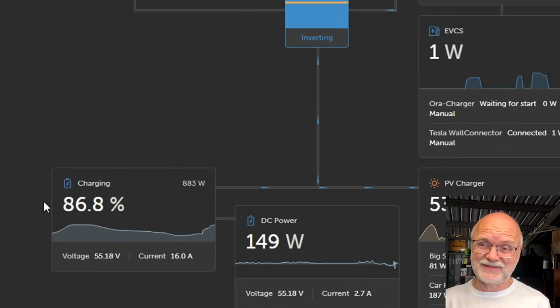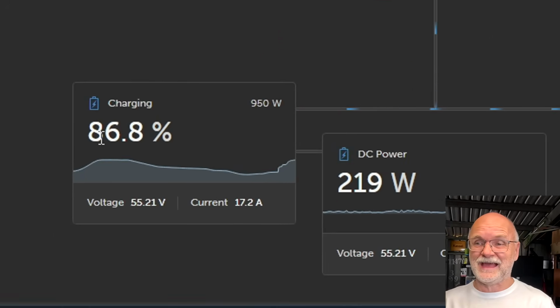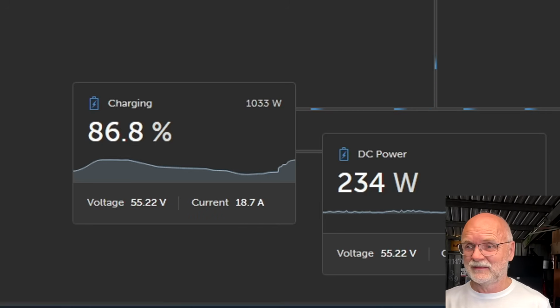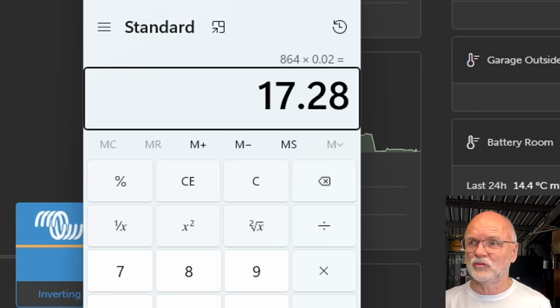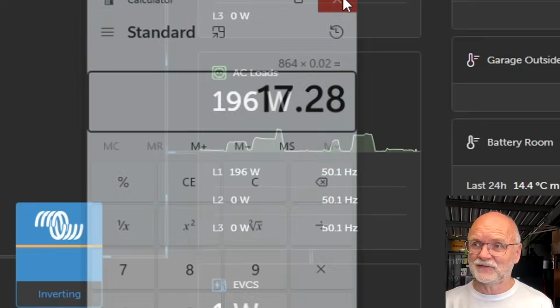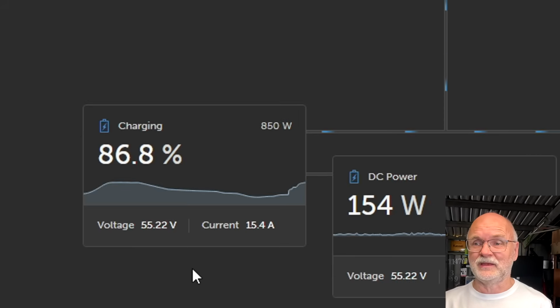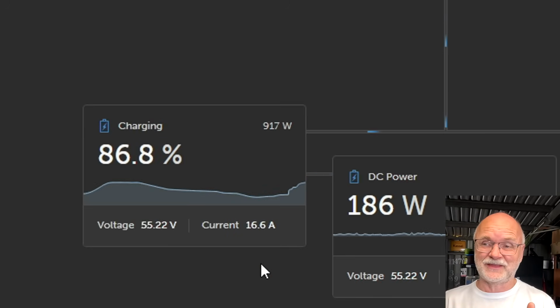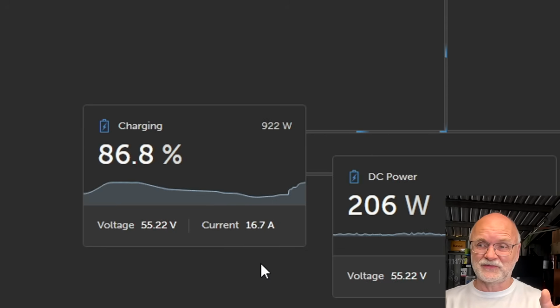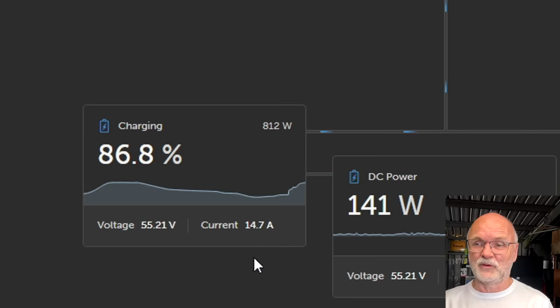So we are at 87%, plus 13 makes 100, so we are very close. The current needs to go under 17.6 amps. Is that correct? 17.28 amps for 3 minutes, and then the Smart Shunt would reset to 100%, but it hasn't done it yet. Because if it goes over 17.28 amps again, just for a split second, within these 3 minutes, it starts this timer again.